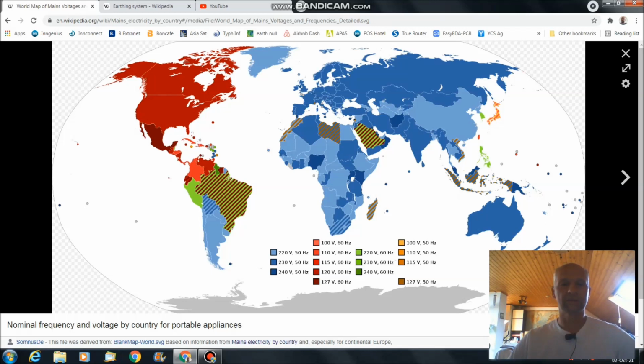And then we have the other parts of the world, which have either 220, 230, or 240 volts. So on average it's a 230 volts line to neutral voltage, about double the voltage of the Northern American system. What this actually means when it comes to protective systems, we will see in a moment when we talk about protective earthing, and also when it comes to protective devices like RCDs, GFCIs, etc.